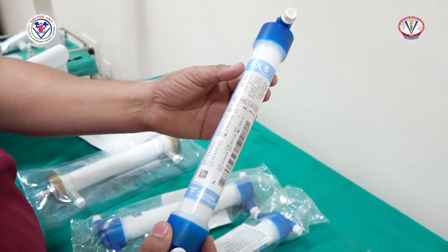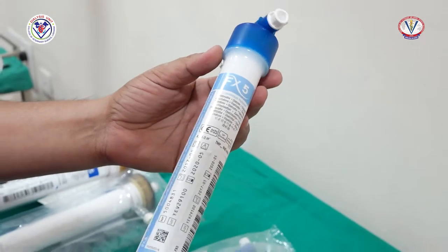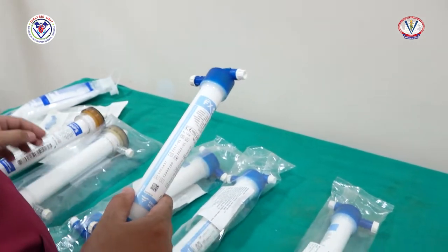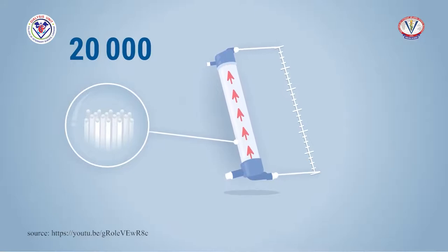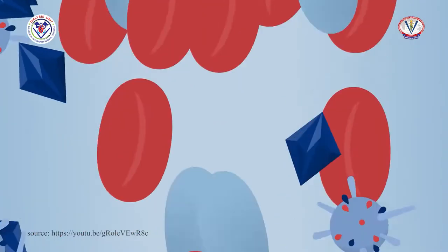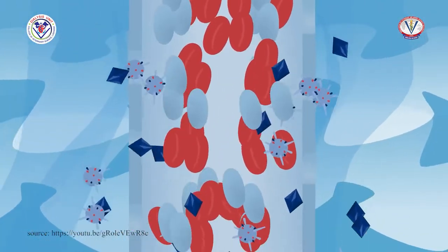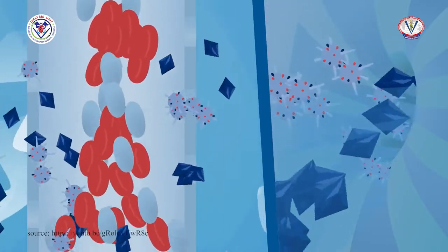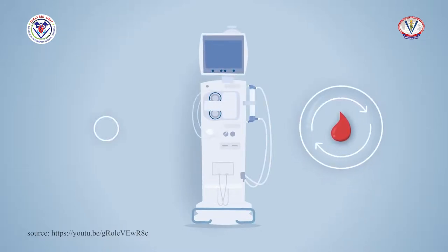Another important component of dialysis is a dialyzer, which is also termed an artificial kidney. Inside a dialyzer, which is approximately 30 centimeters long, or about 12 inches, the blood flows through up to 20,000 hair-fine fibers. Microscopic pores in the fibers filter out metabolic wastes and excess water, which the dialysis fluid then carries away.